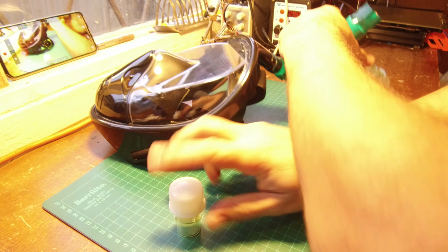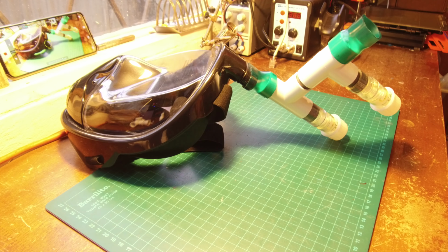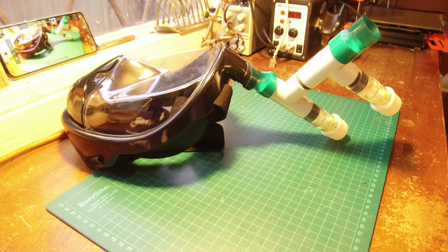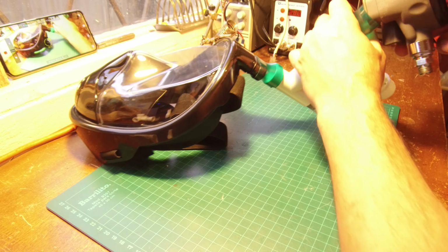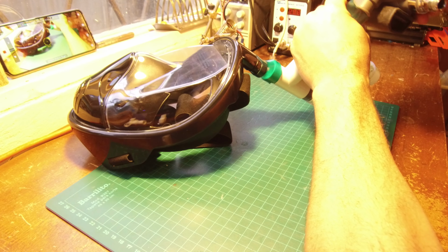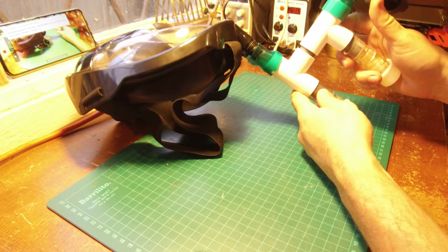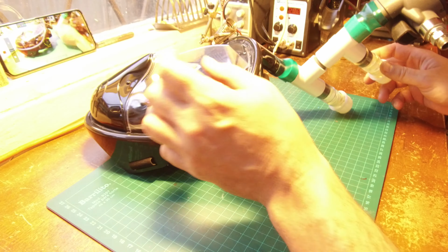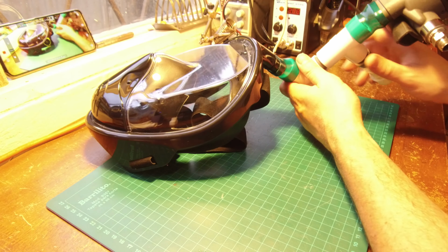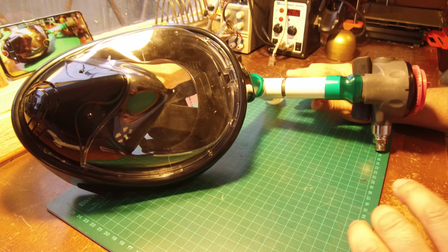Valves are very important. I always put 2, because if there's no pressure relief, your patient's, the user's, lungs might explode, because they're going to get all the pressure from the device. If something goes wrong, always put 2 for redundancy. You don't want a pencil getting stuck there or some garbage and having someone's lungs blown. Basically this is how it works.